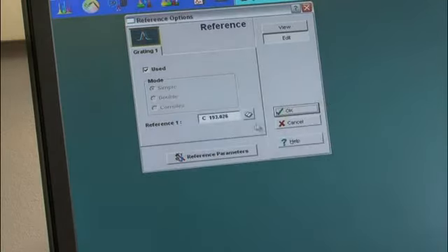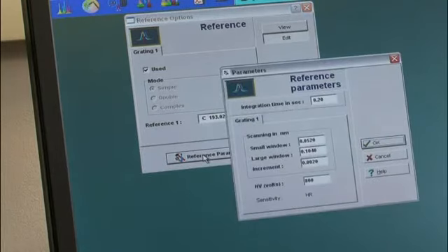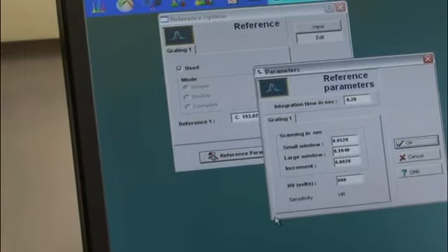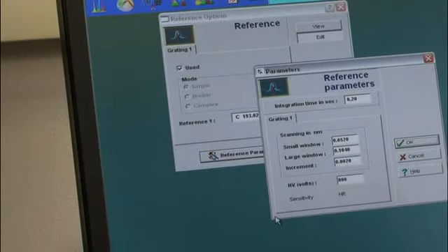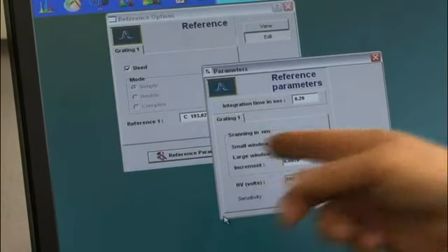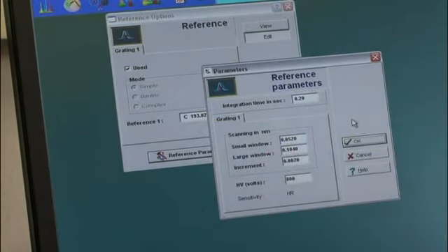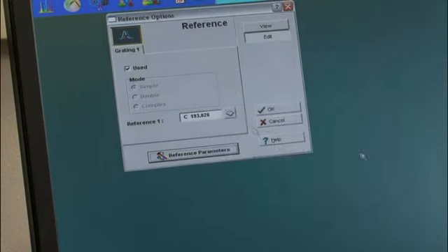So we're not going to change that. If you need to change it for some reason, say you're running a matrix, an organic matrix is going to have more carbon in it than an aqueous one. Basically, that's the only reason you would change it. You would change the reference wavelength if it's presenting an interference in this area, or if it's causing a high background because of your matrix. So you could change it to another element.